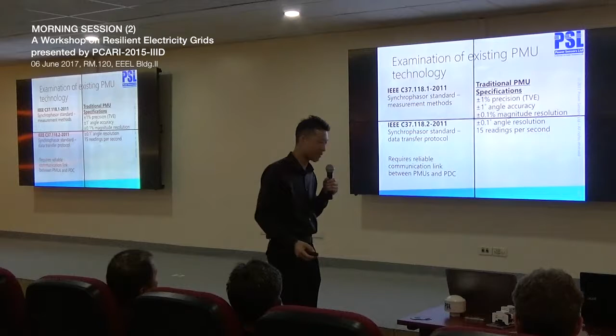Before we developed the micro PMU, we had to examine the specifications of existing PMU technologies on the market. What we found was all of the PMUs were roughly 1% TVE, plus or minus 1 degree, which is perfectly fine for transmission, where I thought the phase angle differences were 5, 10, 15 degrees. But as Sasha's map points out, we actually see phase angle shifts of plus or minus 50 degrees on the transmission, so I learned something new today. But basically, for that type of application, these specifications are more than enough.